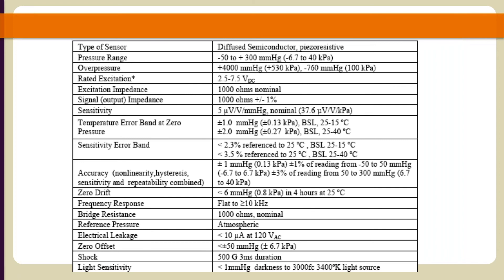I did get one question from Michael Mancuso. His question is: what is the range of filtration needed on the bridge circuit? Most of the filtration is done through software. If you're doing clinical cases, the TC510 interfaces to the cath lab's clinical monitoring system and runs through the software filter on the clinical monitor. If you're using LabChart — we're partnered with AD Instruments — you could run a 50 Hz low-pass filter to filter out noise. Our PCU2000 also has a built-in filter that helps reduce noise, but most of the filtering would be done through your software.